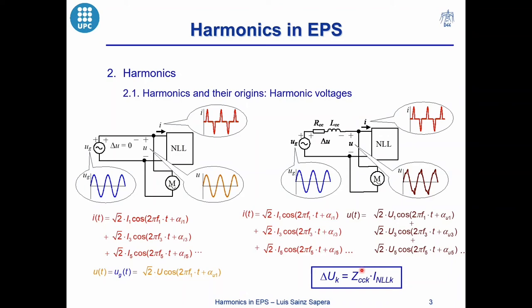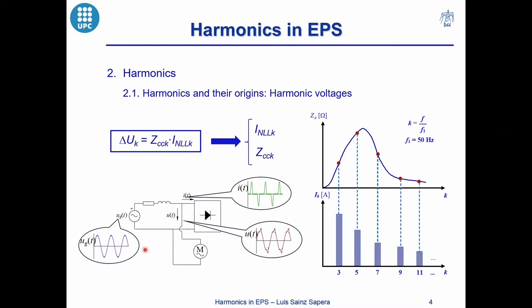This means that the harmonic voltages depend on two factors: the RMS value of the harmonic currents and the value of the grid impedance. If one of them is high, we will have large values of the harmonic voltages, and these voltages become highly distorted. For example, the value of the impedance depends on the frequency. If we have a peak value of the impedance at one of the frequencies of the harmonic currents injected by the nonlinear loads, we could have a harmonic problem with the voltages.